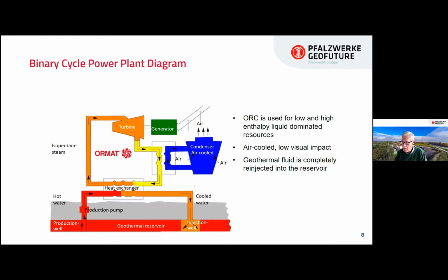As you know, we have two different circuits operating in a binary power plant. In the background we have the closed brine circuit, where we produce brine at 165 degrees Celsius and 20 bars on the production side. We extract heat from the brine in a group of heat exchangers, which we'll see in more detail later, and transfer the extracted heat to a second closed circuit, the organic Rankine cycle, which in our case is operated with the working fluid isopentane. This is vaporized in a group of vapor heat exchangers, and the vapor drives a turbine directly connected to a generator. After expanding in the turbine, the vaporized isopentane has to be condensed back into a complete fluid in a large air-cooled condenser, and then the whole circuit starts again.